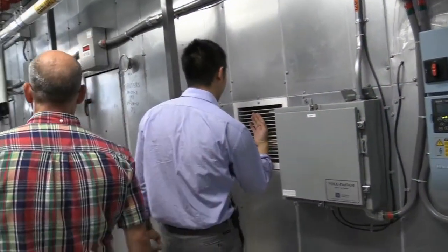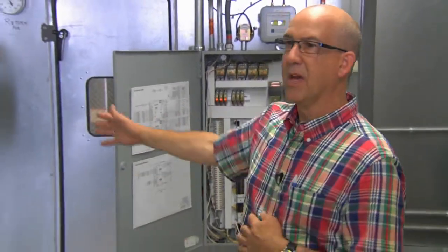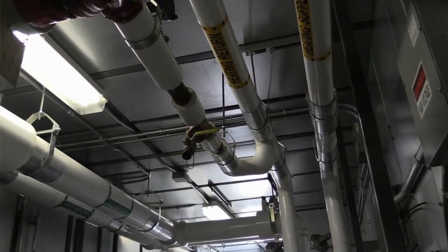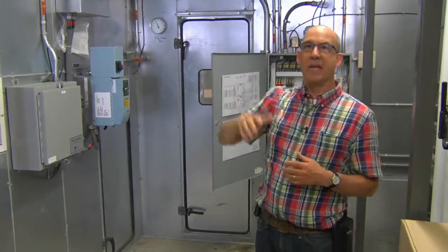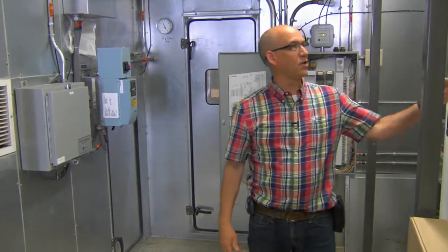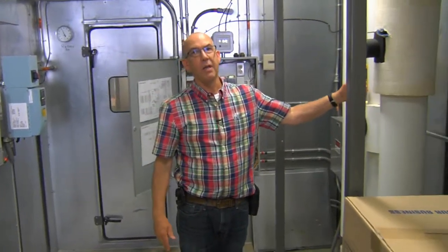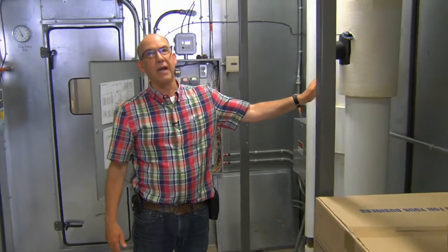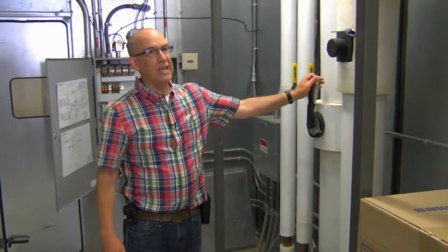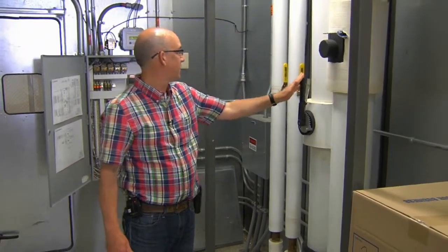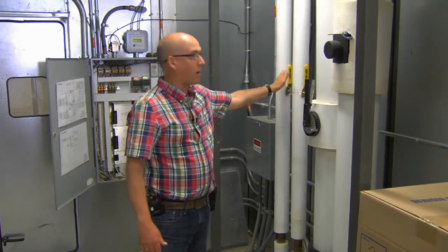So we're here in air handler number 9, and inside this air handler, there's actually a separate room. The air handlers are on my right. We have behind us the control panel, a VFD for the return fan. We have some piping, a heating coil up above us here. We have insulated pipe. We have isolation valves on chill water piping right here. And what we're trying to make sure when we're walking down a mechanical room is isolation valves should be fully open, as we see here and right here on the hot water loops.